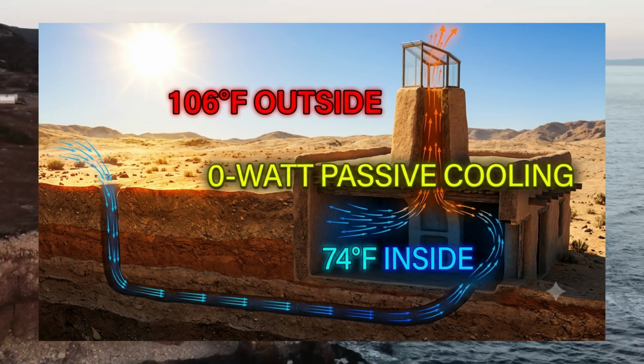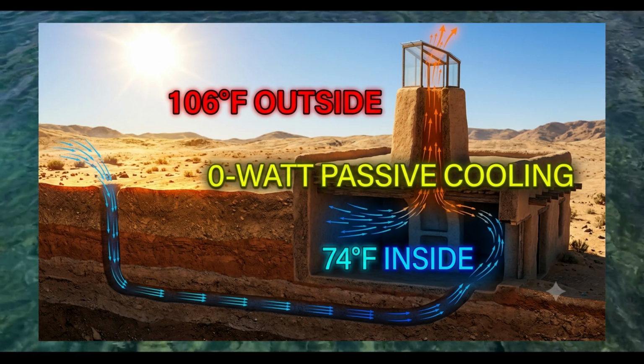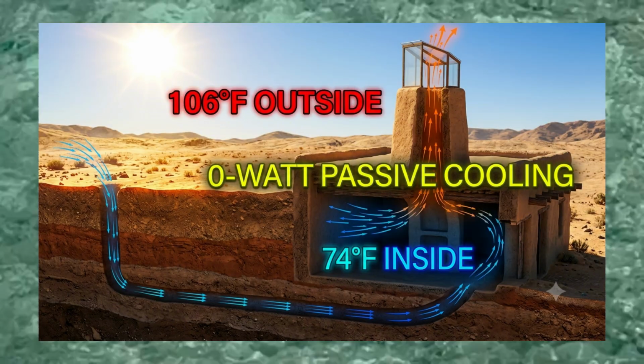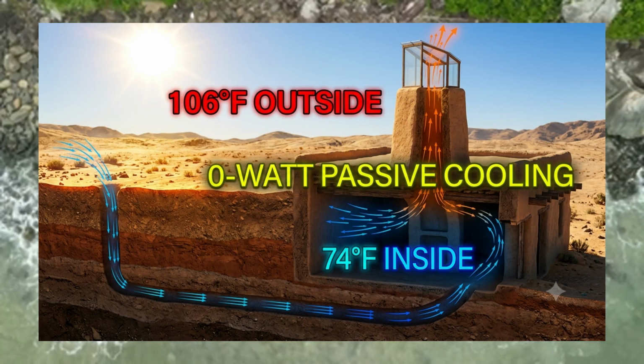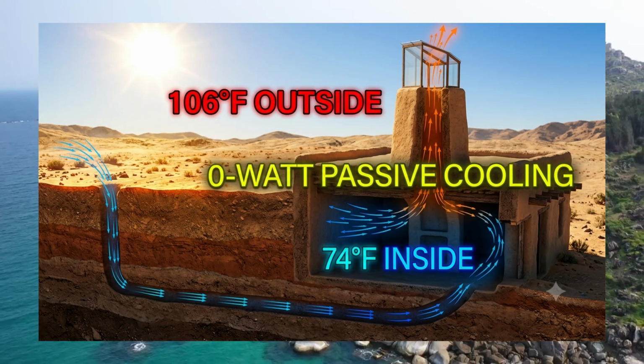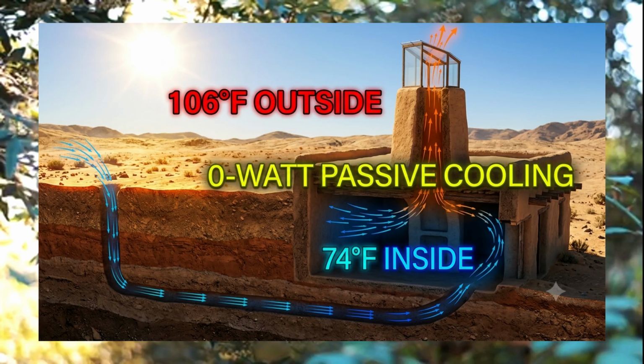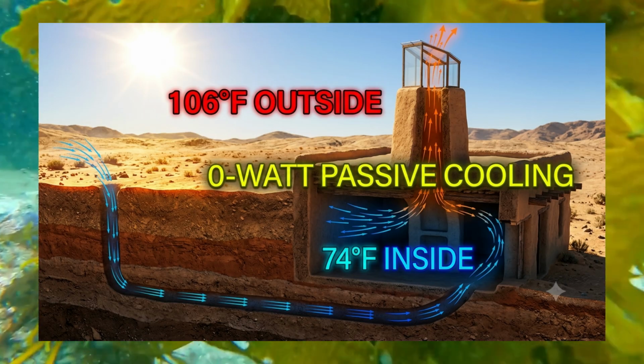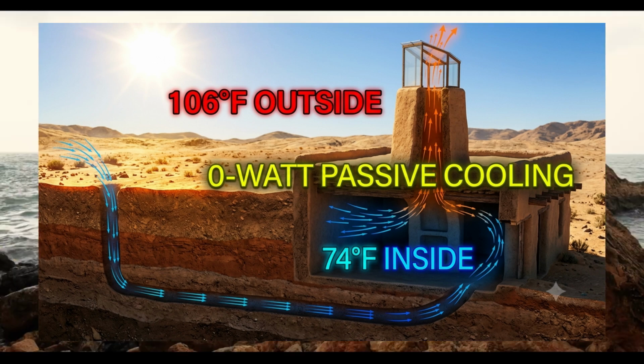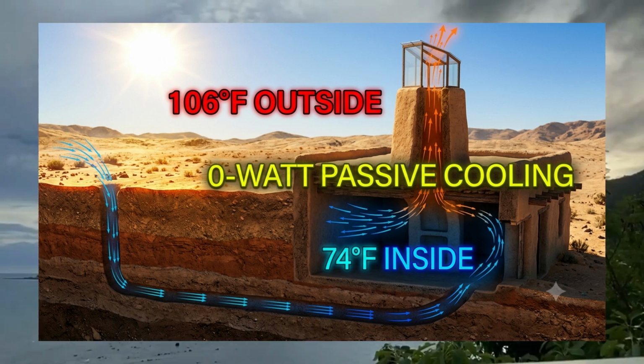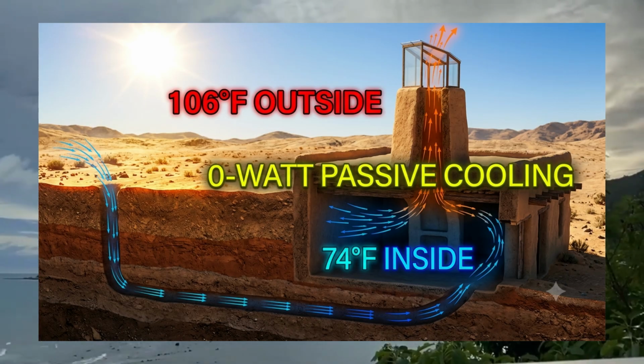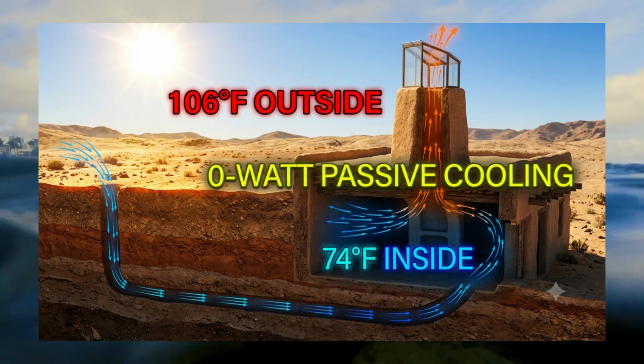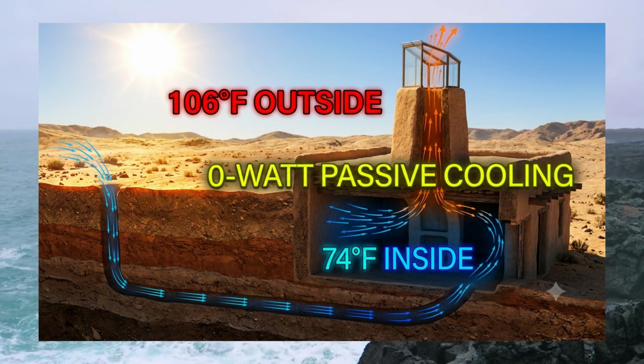A properly functioning solar chimney behaves like a continuous, low-power vacuum cleaner, constantly drawing air out of the building's interior. This means that when the system is operating at peak efficiency in the middle of a hot summer afternoon, the entire living space of the home is under a state of mild negative pressure relative to the outdoors. In a modern, highly sealed home, this negative pressure is where extreme danger begins.